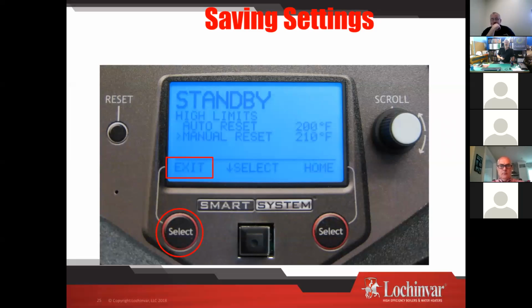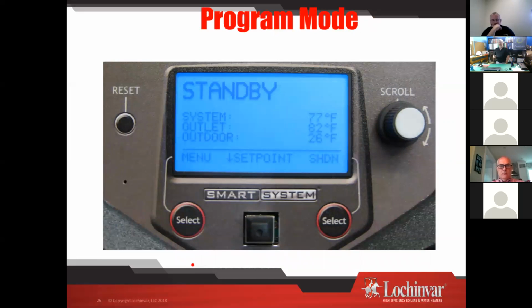Whenever you're done doing any of your programmer settings, you hit that exit button and it'll take you back. Home takes you to the home screen. And when you do that, you will see a message that says parameters uploading. That lets you know that you've done it correctly. So after you've made all your changes, you hit that, you get parameters uploading, you know that you're putting all of your stuff up on the board, moving it to the main board, if you will, from your display. Because as we program all our stuff, we hold that programming in the display instead of dumping each and every one into the main board. And the reason for that is in our original control, every time you made an adjustment, the boiler would start and stop, because we were programming to the board. It stopped, we uploaded. So now it holds everything in the display. When we're all done, it's going to dump it to the main control board. It will turn off and back on as far as the firing of the boiler. So that's why we do it that way now. If you forget to upload your parameters, though, at the end of the day, it doesn't hold it for you. When you come back next day, you're going to have to add them all again.